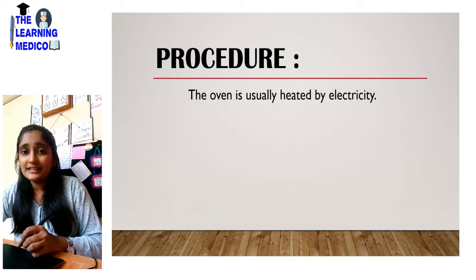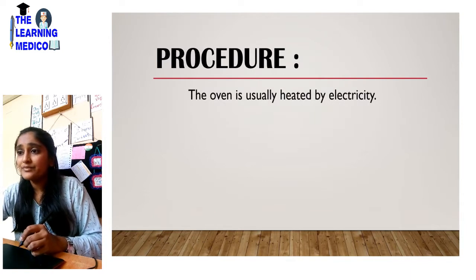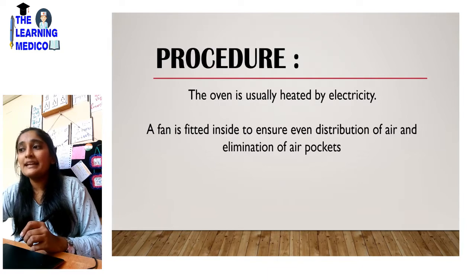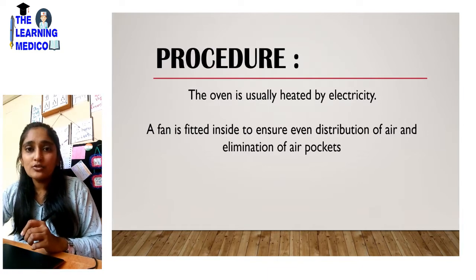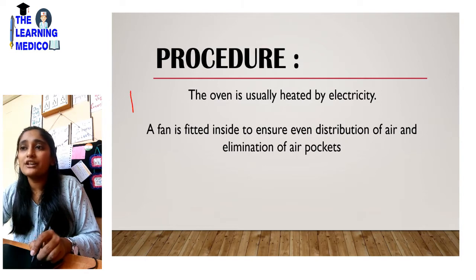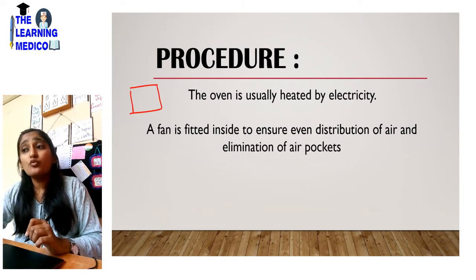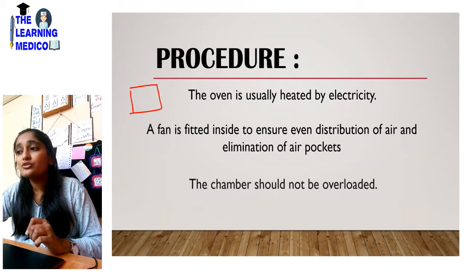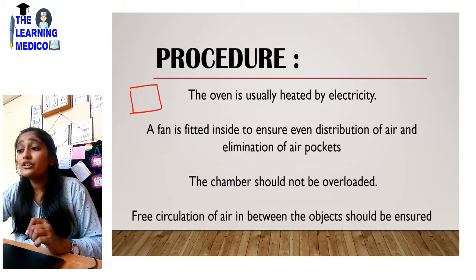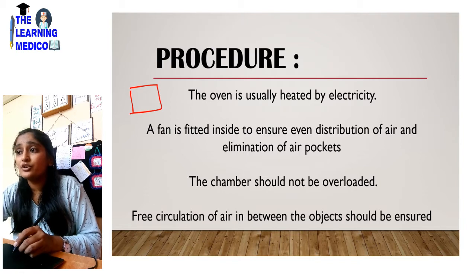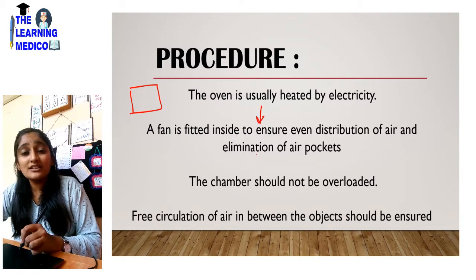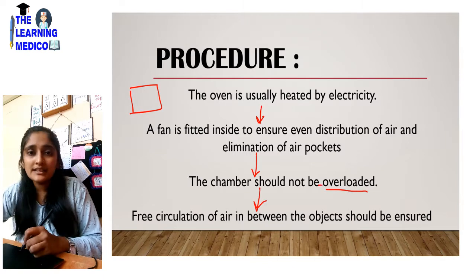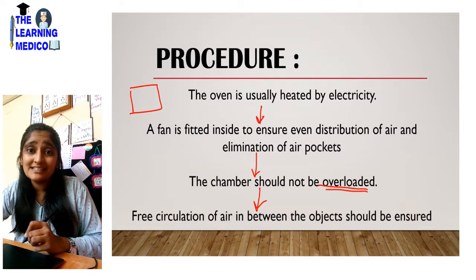The oven is usually electrically heated. A fan is fitted inside to ensure even distribution of air and elimination of air pockets in the chamber. The fan ensures that heat is equally spread in the chamber, and the chamber should not be overloaded — free circulation of air between objects should be ensured.